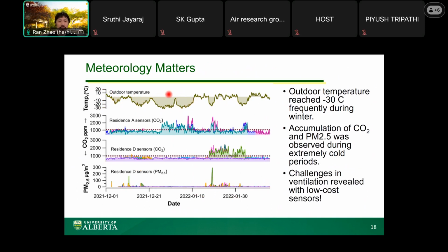What we saw is that when the outdoor temperature is extremely cold at minus 30 degrees, in some residences we saw a jump or accumulation of CO2, or particulate matter in some residences as well. After communicating with resident services on campus, we found that when the temperature is too cold outside, the buildings are forced to reduce the ventilation rate to keep the thermostat going. There's also a chance the fan on top of the building is frozen over, so ventilation kind of stops — that likely led to the accumulation of CO2 and particulate matter.